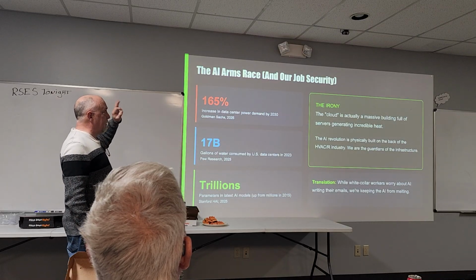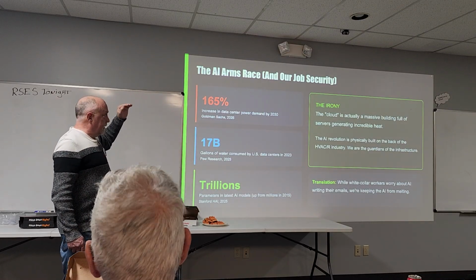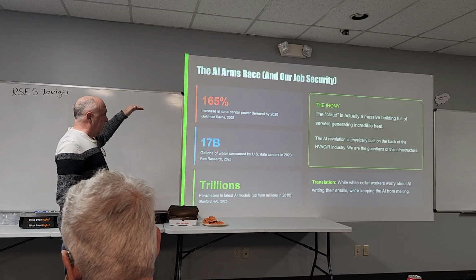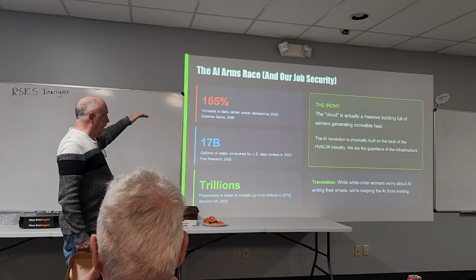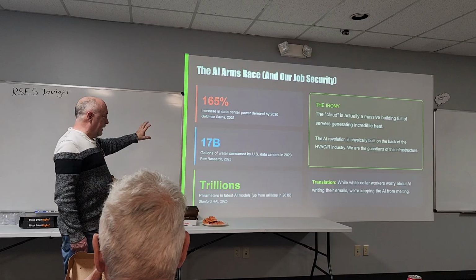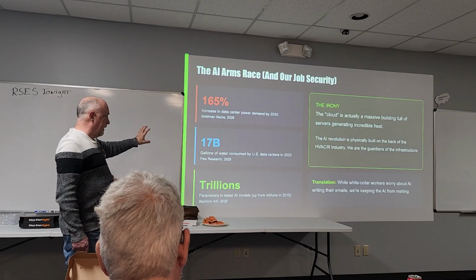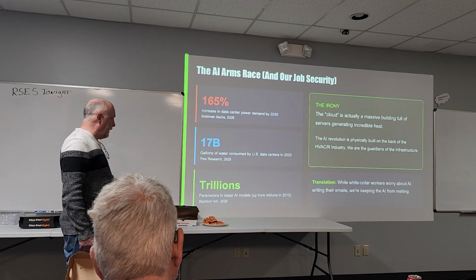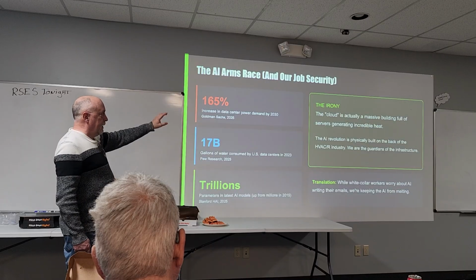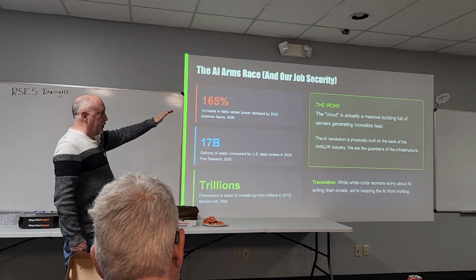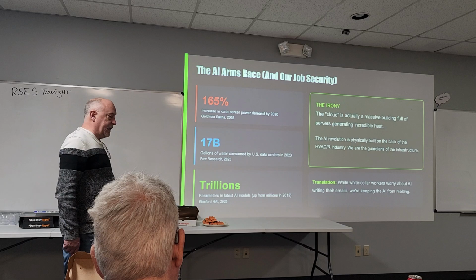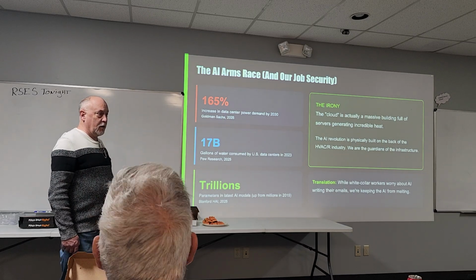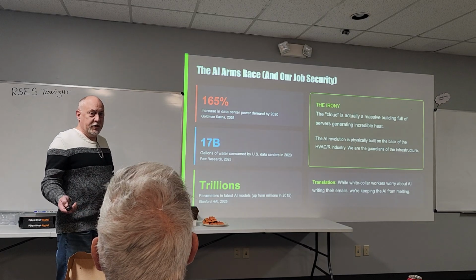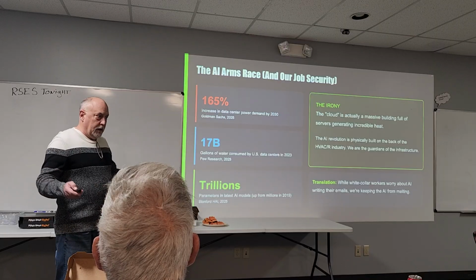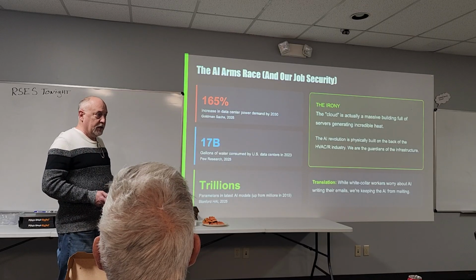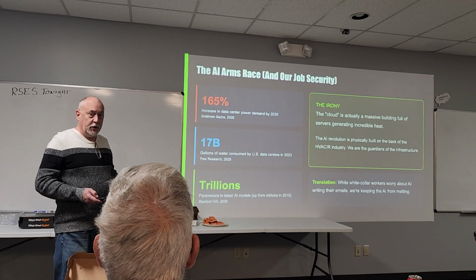But this is coming at a huge cost. A 165% increase in data center power demand, and 17 billion gallons of water that it's gonna take to run this in 2023, with trillions of parameters. And the irony is, it's a massive building full of servers, and for us in the HVAC industry, this is an area we're gonna have to start really looking at, because what are we gonna do with this waste heat energy? In Finland, they're heating entire cities with it right now, because they have use for that heat almost year round.